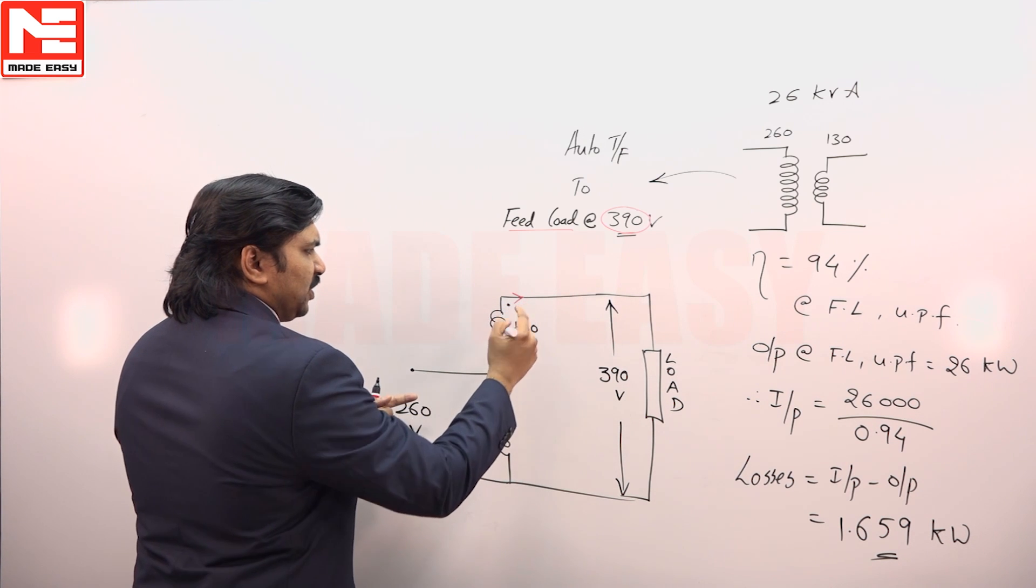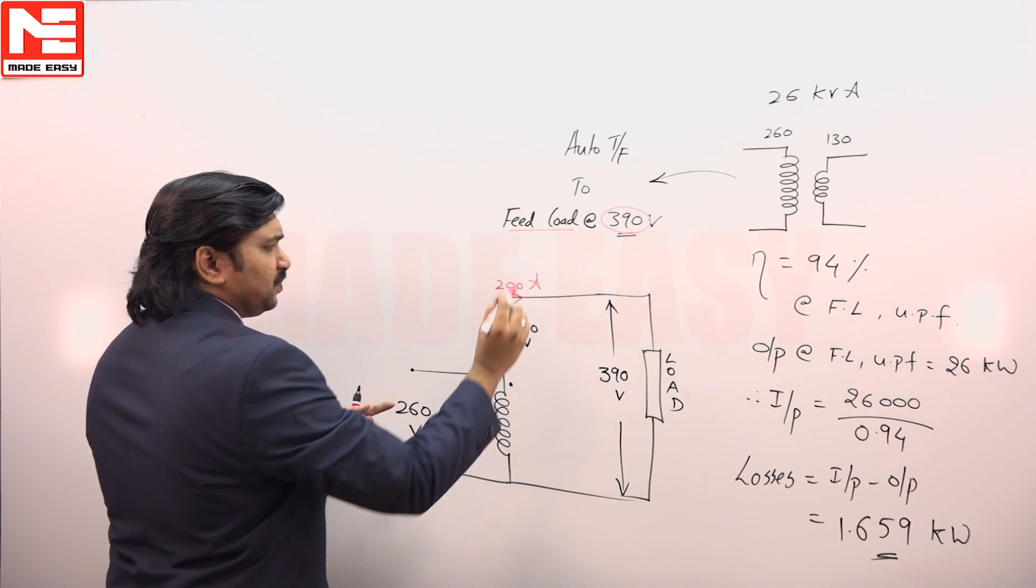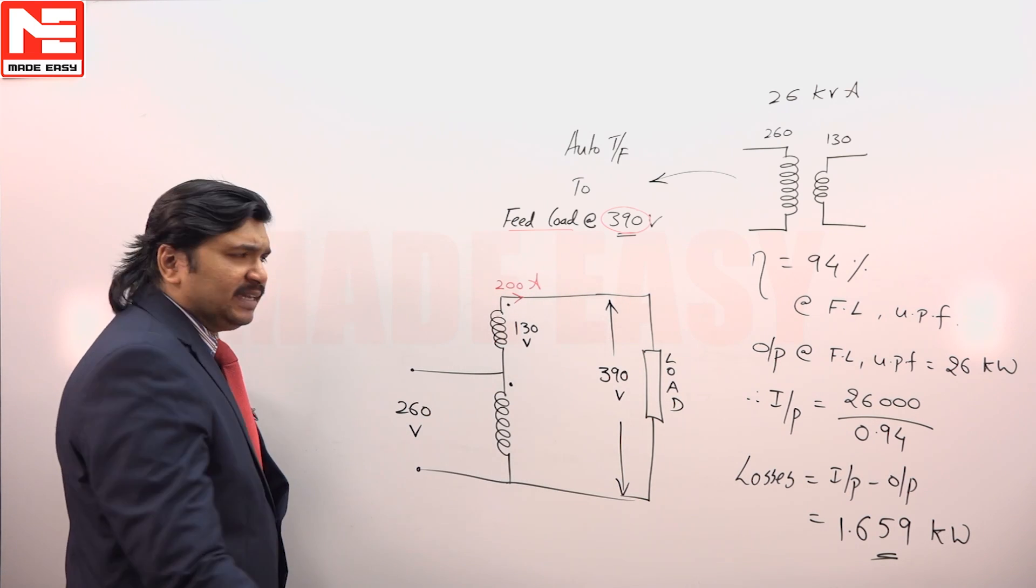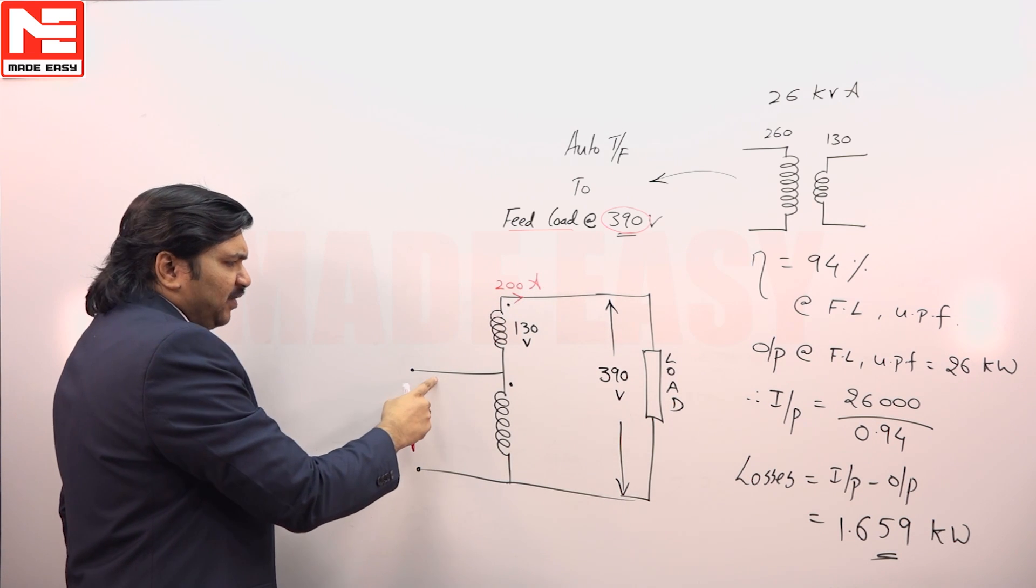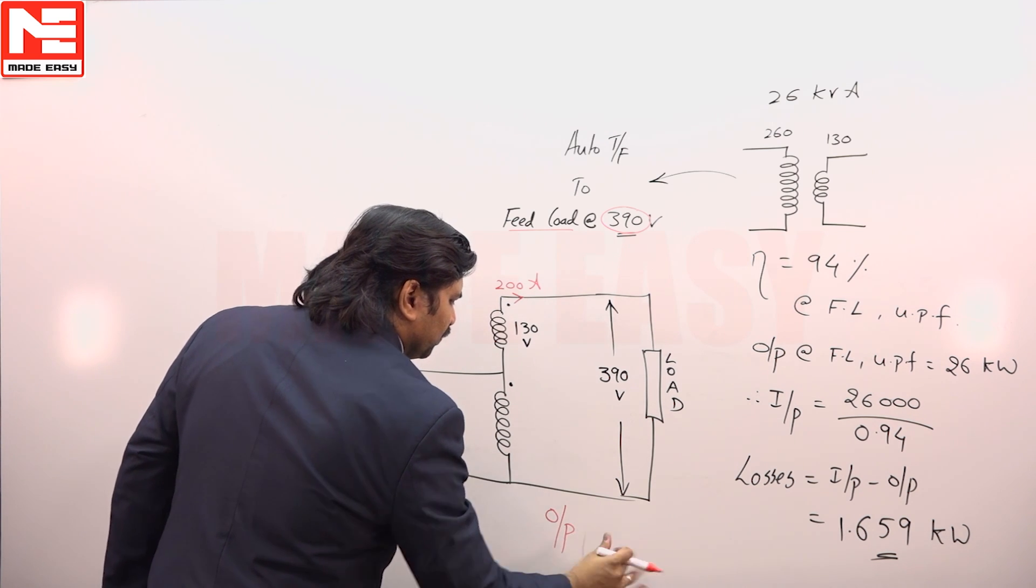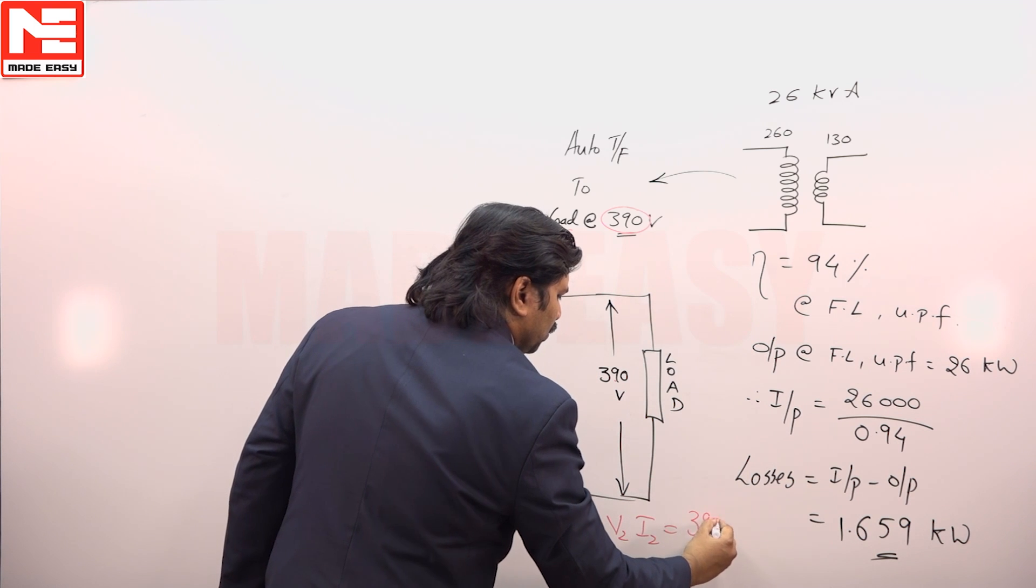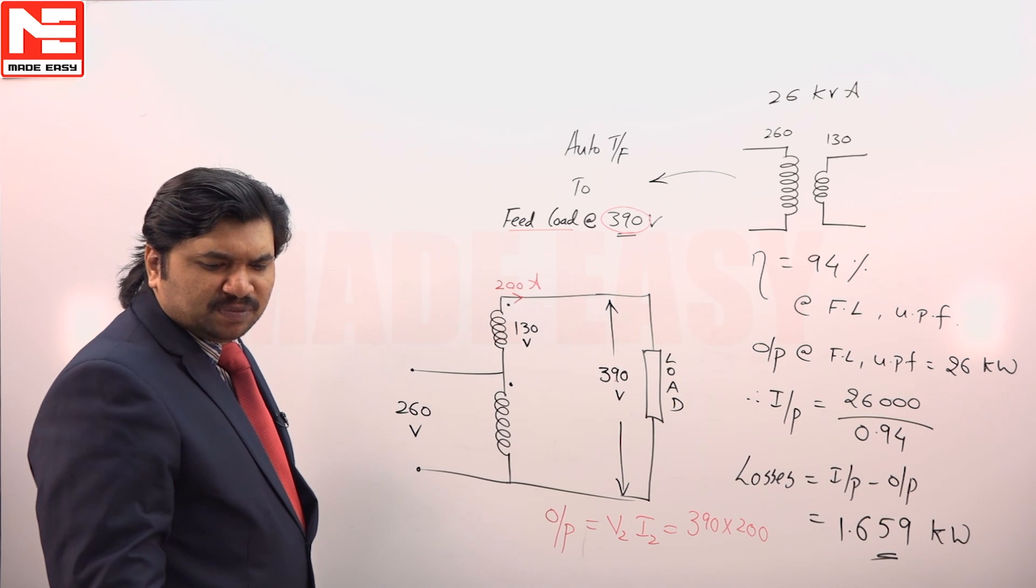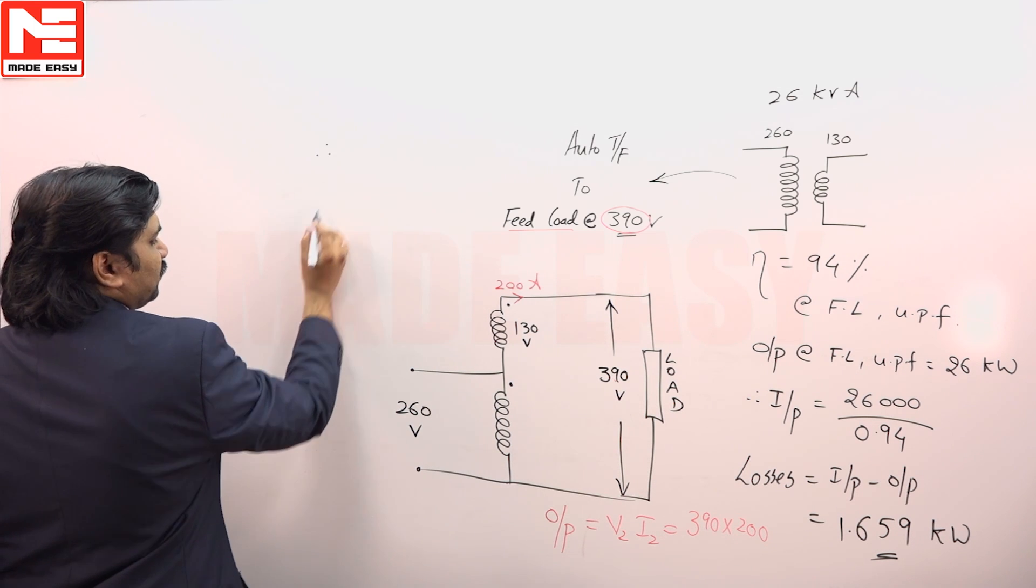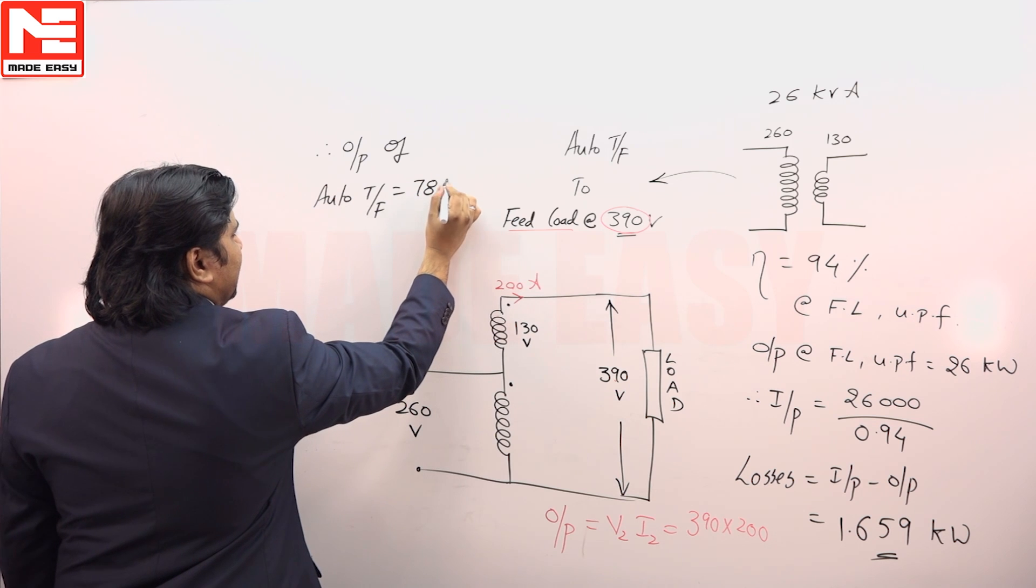The current rating of this 130 volt winding is 26000 by 130, which gives you 200 amperes. So what is the output rating of an auto transformer? Simply V2 I2 or V1 I1. What is V2 I2? That is equal to 390 into 200, which means 78 kVA. Output of auto transformer is 78 kVA.